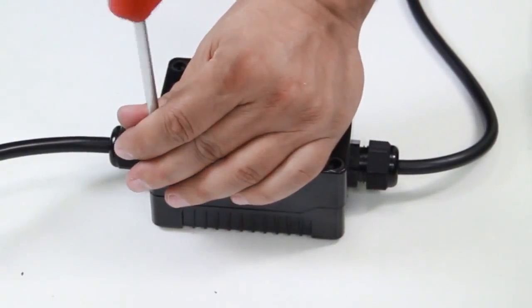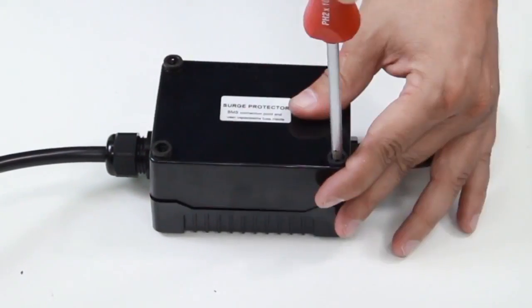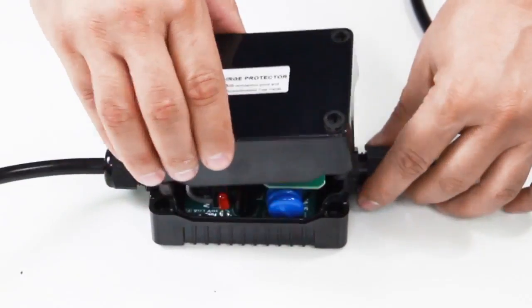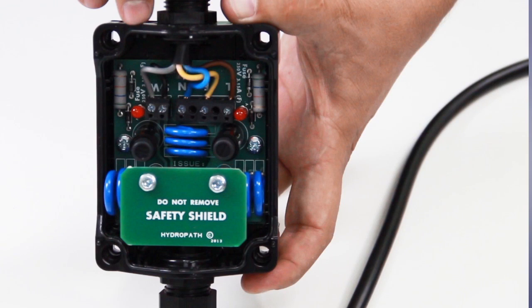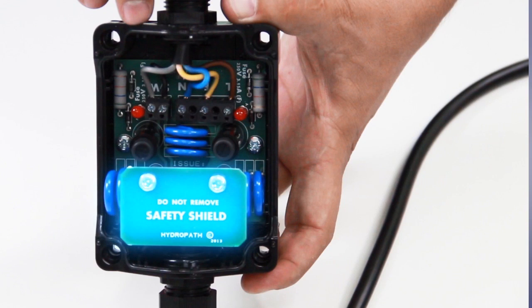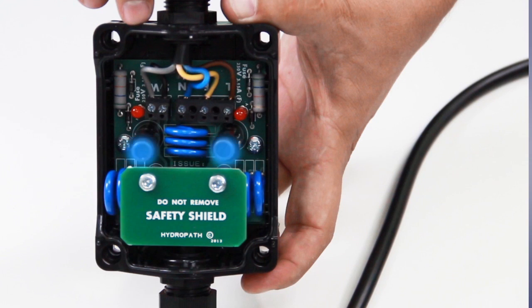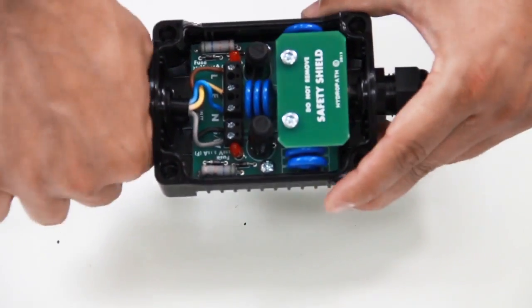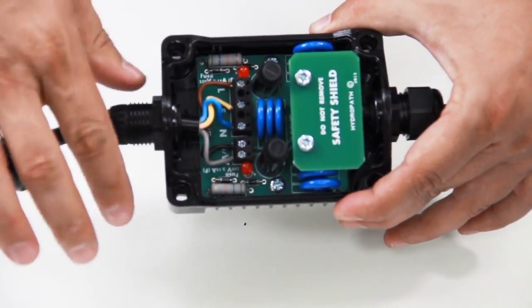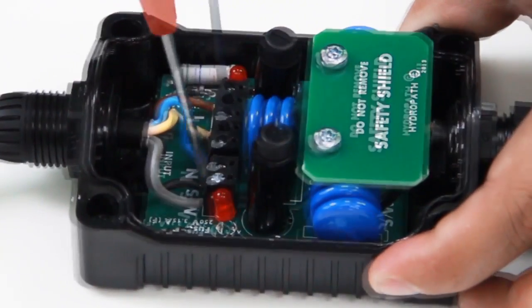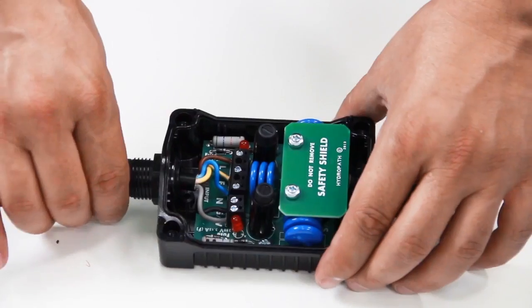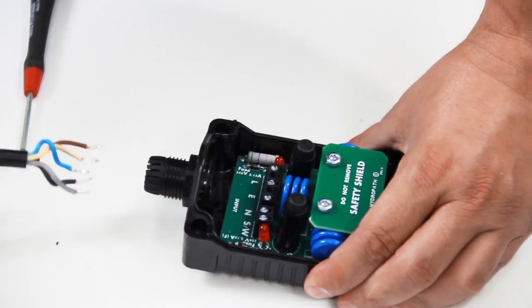Remove the surge protector cover. The surge protector includes a safety shield on top of the connection to the transducer, 2 fuse holders, 3 standard electrical connections, BMS relay signal wires SW. Unfasten the cable gland. Unfasten the screws. Pull out the supplied electrical cable.